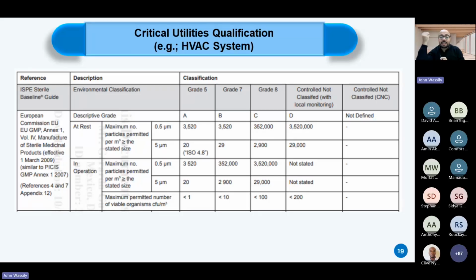By saying HVAC system qualification for a production area, the aim of the HVAC system qualification will be to make sure that the clean room in which I will be preparing, formulating, manufacturing, filtering, or filling the vaccine is actually meeting the predetermined and designated specs for the cleanliness level. So, for example, for a preparation room, for a formulation room, for a vaccine, the conventional used cleanliness grade is grade C. So, by qualifying the HVAC, I will make sure that the HVAC system can meet the cleanliness grade of grade C. This is by using particle counters and measuring the concentration of particle inside the clean room.